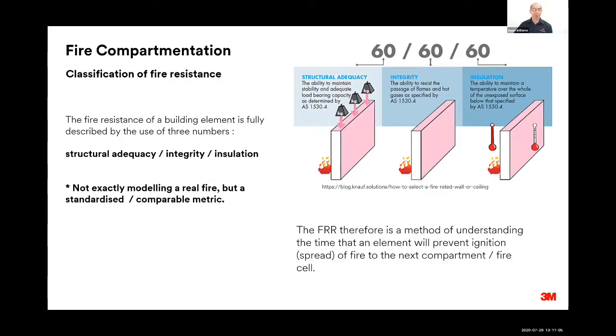So the nomenclature of the fire resistance rating, the three numbers there represent the structural adequacy, the integrity, and the insulation. So in the example there, structural adequacy, the element being tested cannot collapse in that time in the fire endurance test. The integrity talks about not allowing any sparks or gases or flames to pass from one side of the fire affected compartment to the next. And the insulation describes how long the element can resist the flow of heat from one side to the next. And that's usually a temperature change of 180 degrees in a standard fire endurance test.